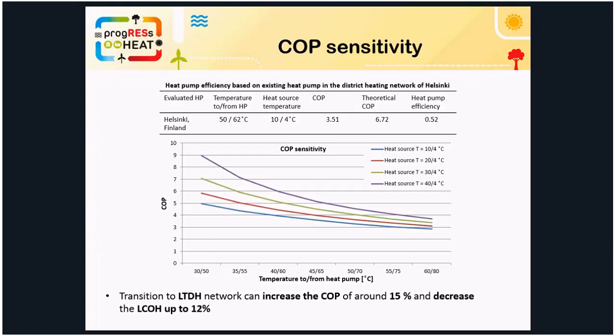In the next step, we have analyzed the COP in more detail. As mentioned before, in this graphic we are on the right side, in the temperature levels of around 80 degrees Celsius, and based on the different heat sources, we can see that COP in the current district heating network can vary from 3 up to 4. In order to increase the COP, we have to make the transition to low temperature district heating networks. That will have an additional positive influence on the cost of heat of the heat pump.